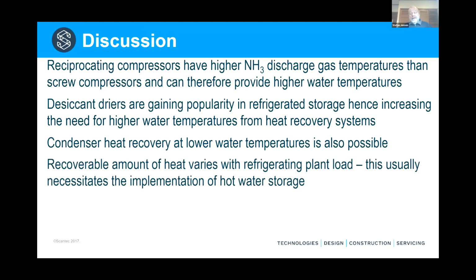The recoverable amount of heat, of course, varies with the plant load. We try to make part load performance highly efficient because that saves energy on the refrigeration plant. And when the plant reduces in load because it's nighttime or it's a holiday or whatever the case might be, then we need to accommodate that. And this usually happens with storage. So we have hot water storage so we can overcome those periods of low load where we don't recover as much heat as we can at full load.